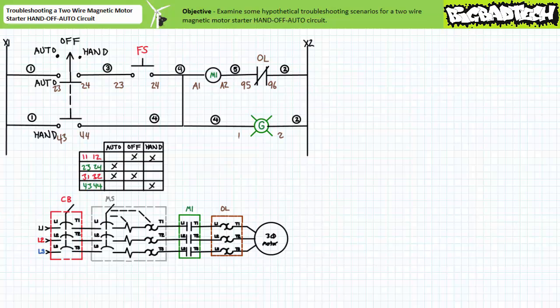While my earlier description of wires as nodes is semantically correct, mission critical operations may need this level of consideration when it comes to routing additional wires. For reasons of robustness and reliability, I would ensure a wire 4 from rung 1, and another entirely separate wire 4 from rung 2, are both landed on terminal A1 of the M1 contactor coil.